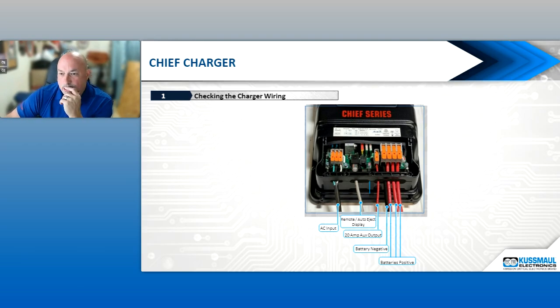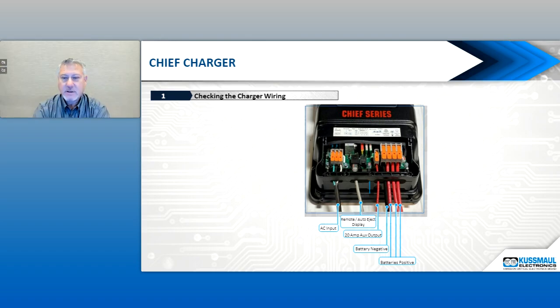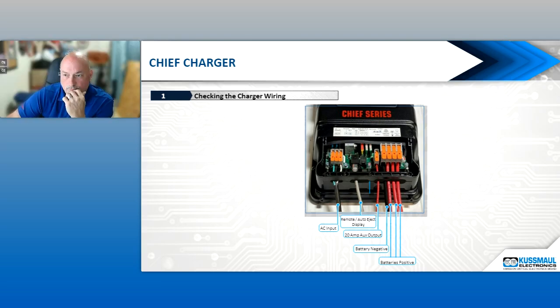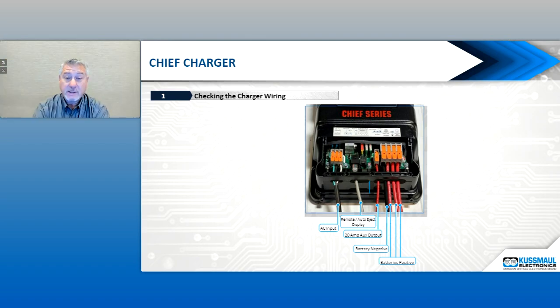Next question: in a typical fire engine, what would be an excessive power parasitic load? That's a good question, it depends, there's no simple answer. If you're getting over 20 amps or 10 amps, would that be anything over what the charger output would be? Good point. If you only have a 40 amp charger and you have 40 amps of parasitic load, that's probably too much. You could always upgrade the charger, but you don't want a parasitic load more than what the charger can handle. It's hard to say though, because with these apparatuses, we don't take anything off of them, we keep adding more stuff that keeps pulling more electricity.